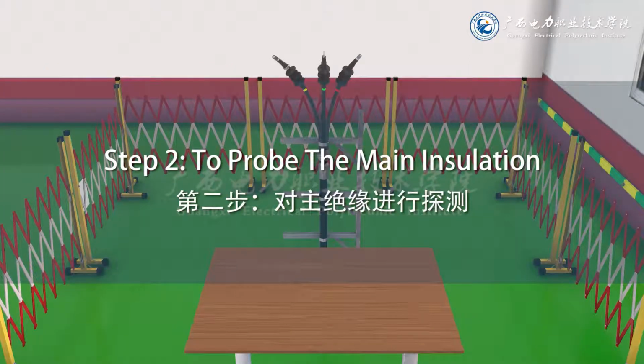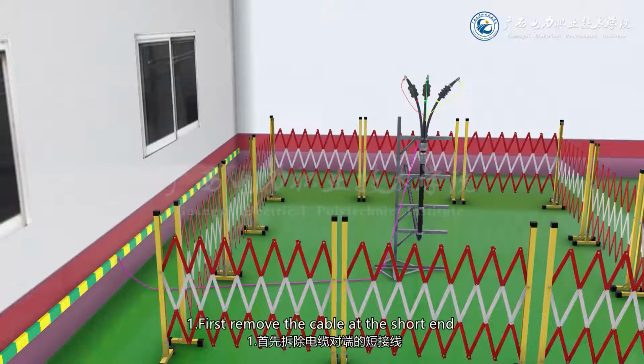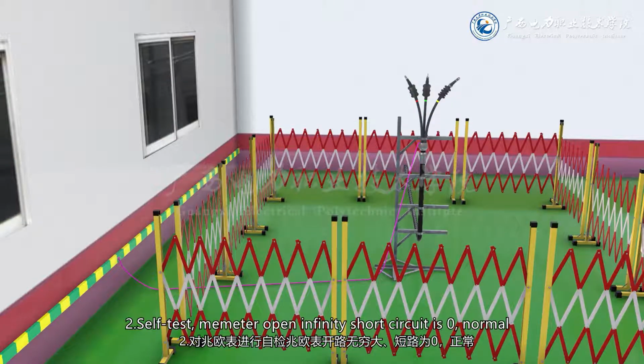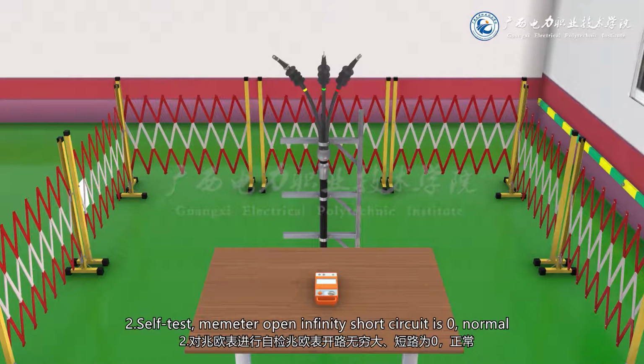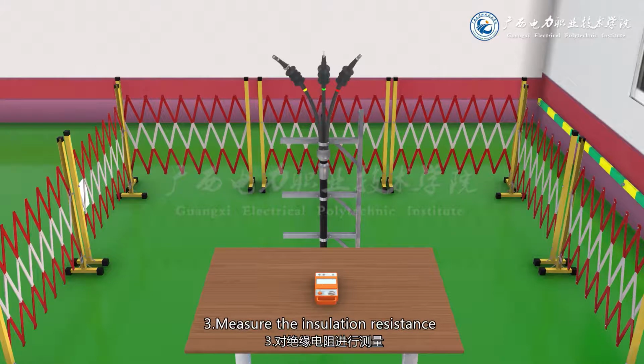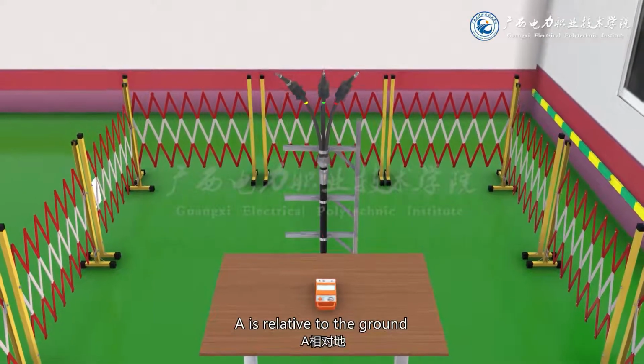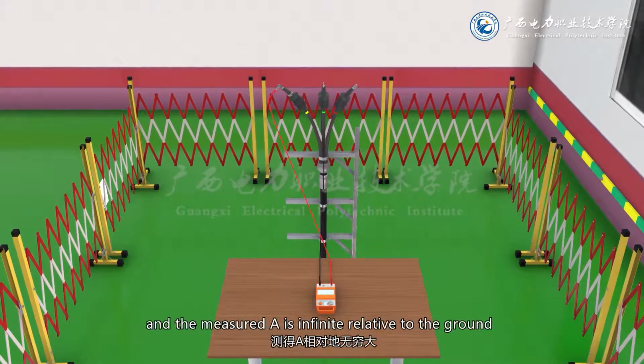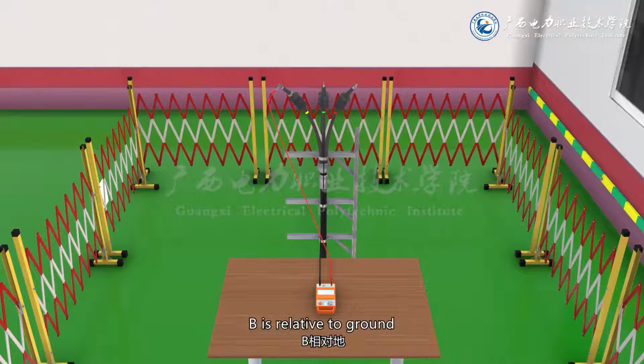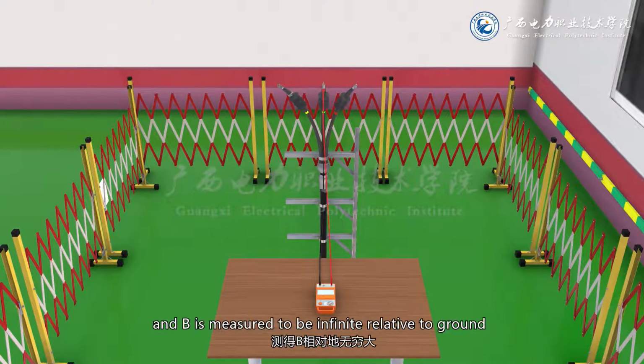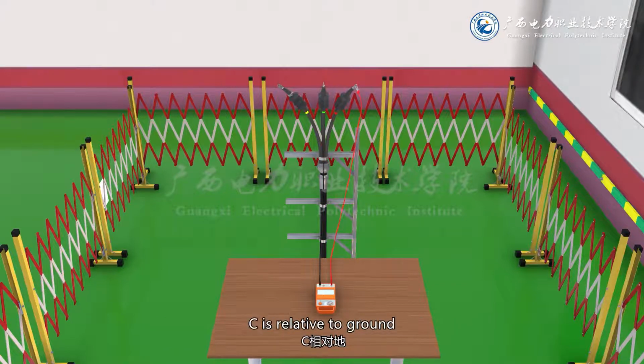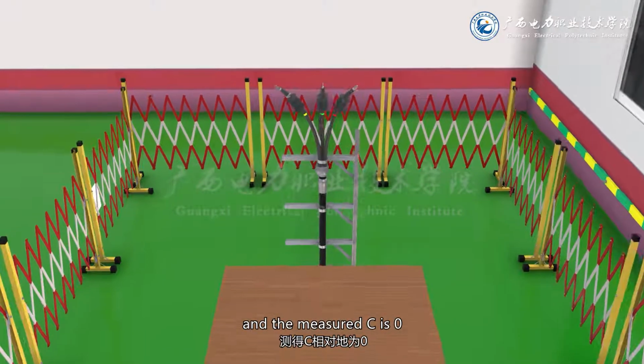Step 2. Probe the main insulation. 1. First remove the cable at the short-connected end. 2. Self-test: the meter reads infinity when open and 0 when short-circuited, which is normal. 3. Measure the insulation resistance. A relative to ground is measured as infinite. B relative to ground is measured as infinite. C relative to ground is measured as 0.